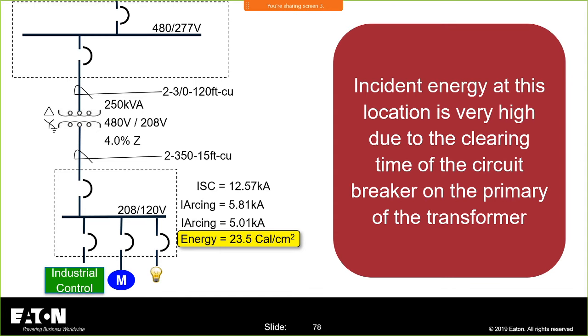Why is this? Understanding the system here, this breaker that's on the line side of that transformer, how do we size it? We don't size that breaker to protect this conductor. We size this breaker to make sure that I don't trip on inrush. I'm going to follow the code requirements, and if I'm in a selective coordination environment, that primary breaker is going to be up there at 250% of the full load amps of that transformer. But in a normal distribution system where I'm not worried about coordination, I'm going to have a primary breaker that's probably about 125% of the full load amps of that transformer.